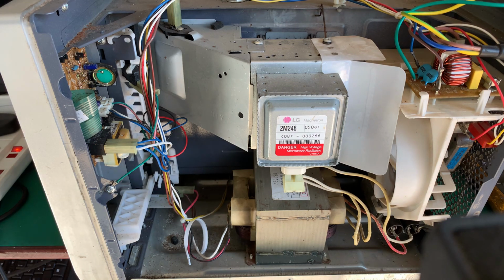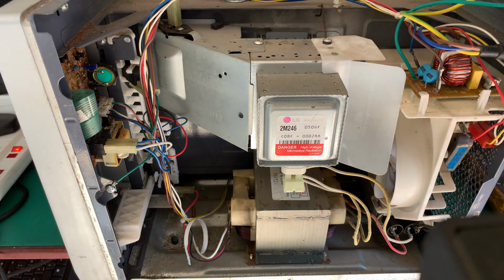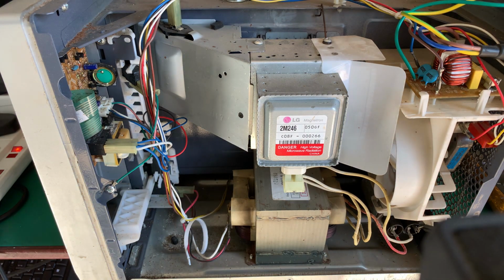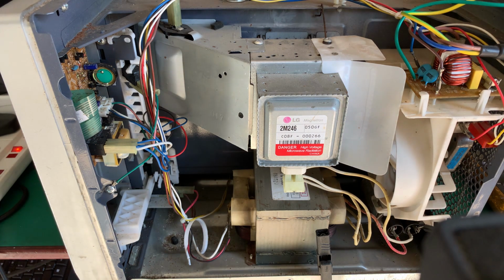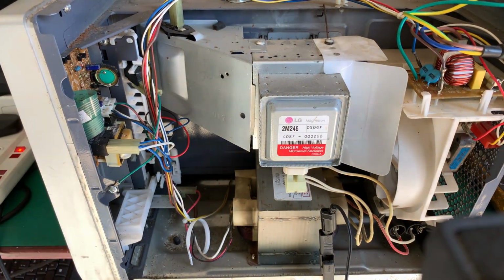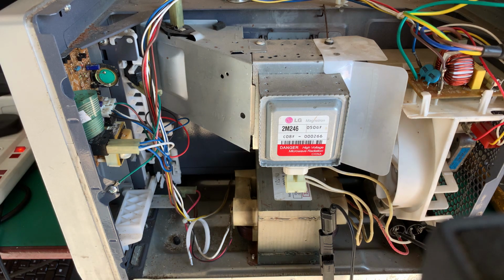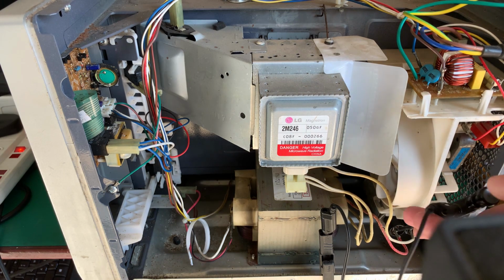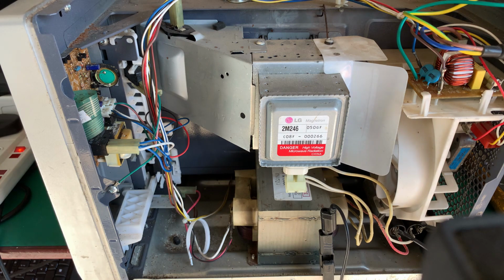It's really not advisable. So what I would advise you to do, if you're going to work on something like that, is get yourself some clamps. You clamp it on here. Make sure that your chassis is connected to earth, and take a lead from here and short out that capacitor, both sides. Just hold it on there. Let's see if we've got a lead here. We'll just clamp it in here. Of course this is not plugged into mains and it's not plugged into earth, but to give you the idea, I'm doing something like that. So you can see the lead is complete, and it would keep the capacitor from charging, because if you do go and put your hands in there, you're going to get a nasty shock, and it could kill you. Like I say, you can have 4,000 volts at that point.